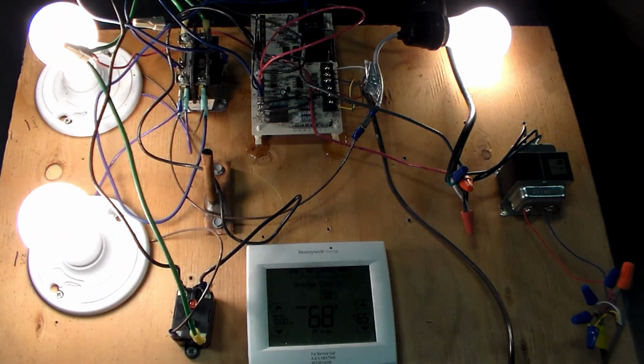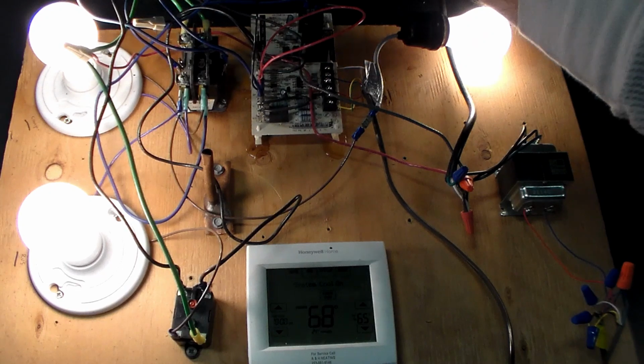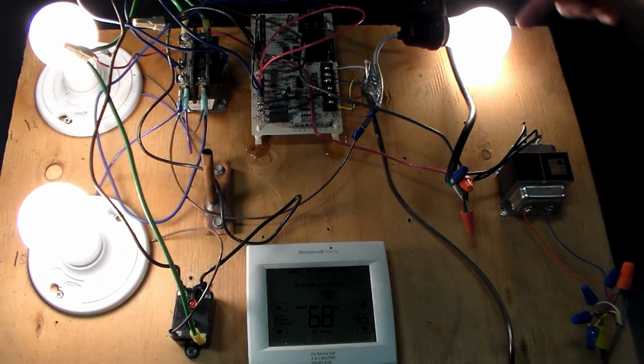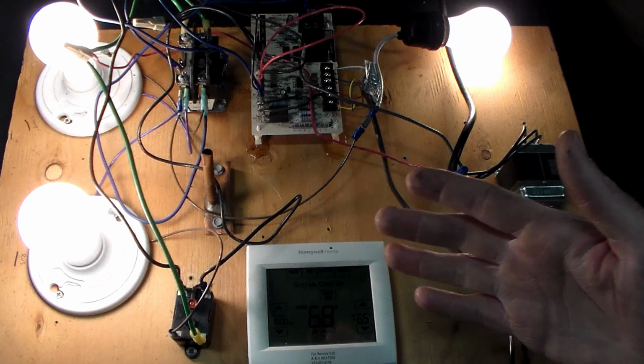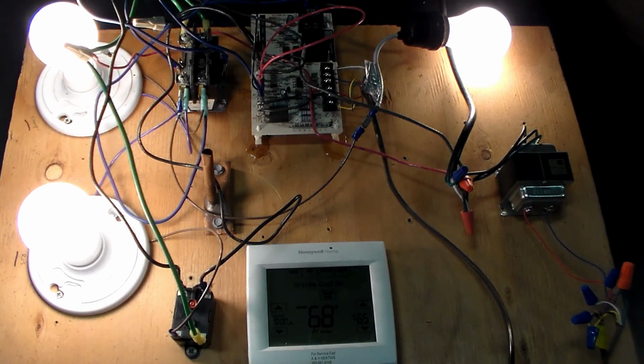But on your typical AC, that contactor is going to send power directly to the compressor and directly to the condenser fan. On a heat pump, it just makes a detour, and it comes off the contactor through the switch on the board before it goes to the condenser fan. So we've got to remember that if we're having issues with our condenser fan on a heat pump, but yet the compressor is coming on, on a typical AC we would go, oh, well, that's a problem with the fan motor because they're wired in parallel directly and there's nothing else in the way. On a heat pump, though, you have to go, wait a minute, is it the fan motor or is it the board stuck open, not sending power to the outdoor fan motor? And then the low and high pressure sensors are simple enough. Defrost sensor is simple enough.